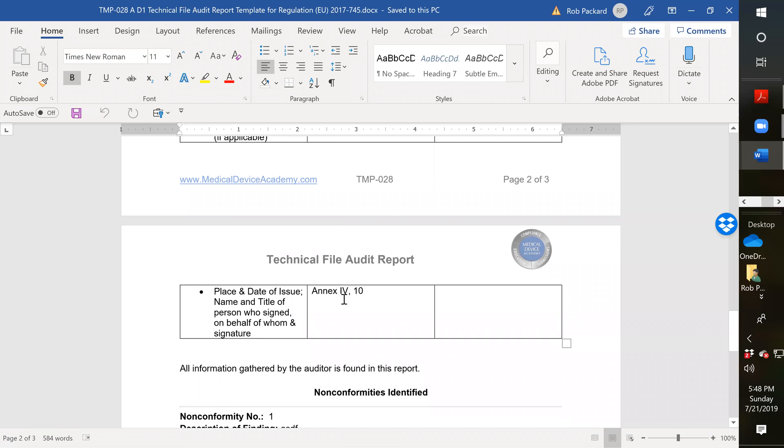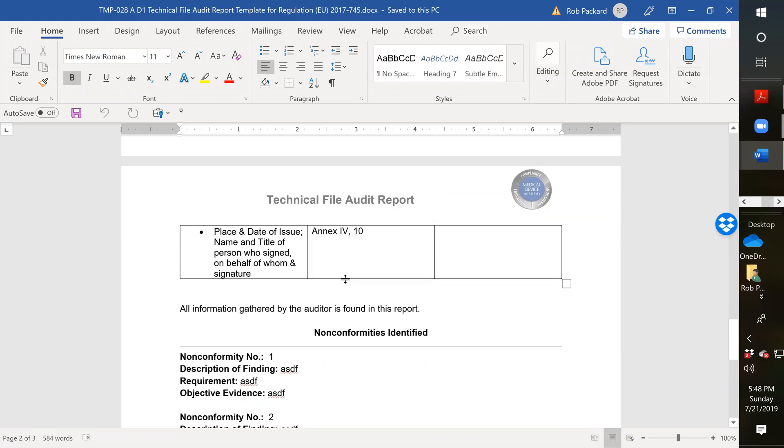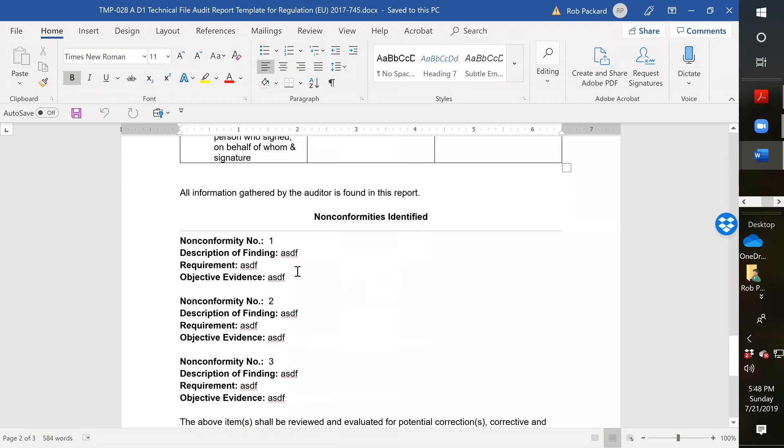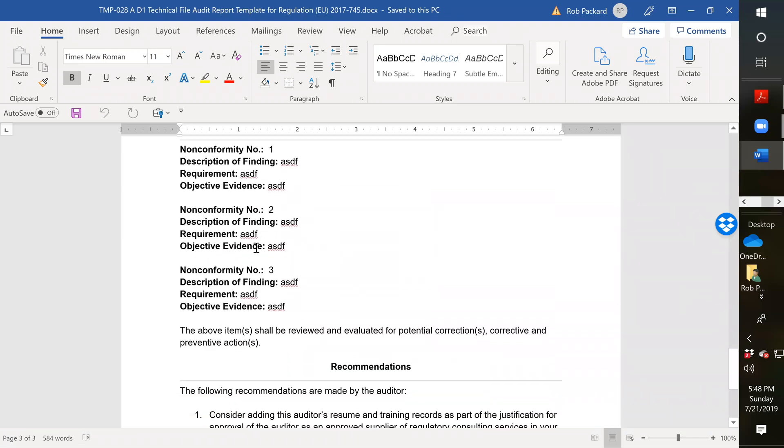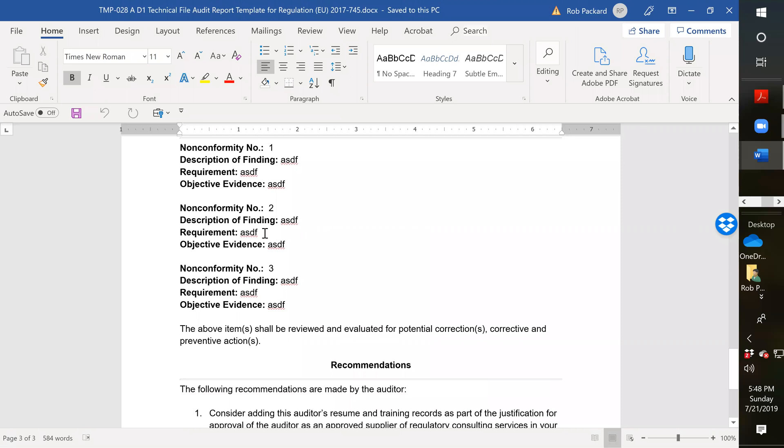And then last but not least, any additional information that's required for that product or by the notified body. And your signature at the bottom. So then I have a place for your nonconformity, so you would indicate, you'd put a copy in of what the requirement is, briefly summarize what's missing, and then provide detailed objective evidence of what's missing.